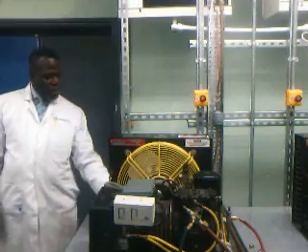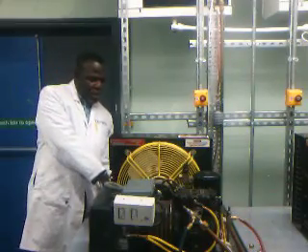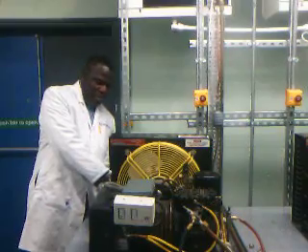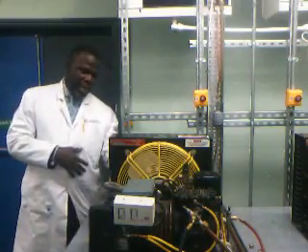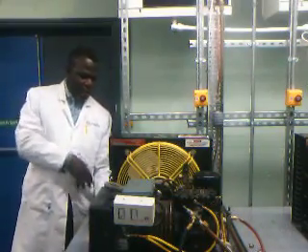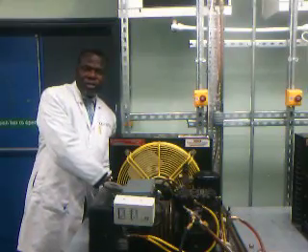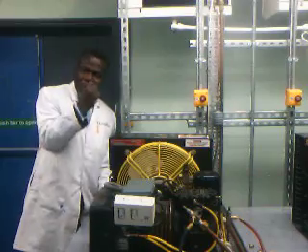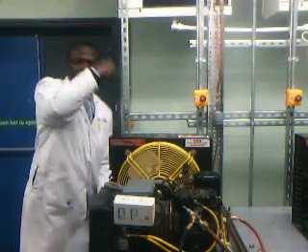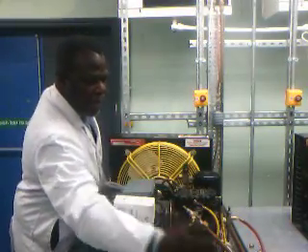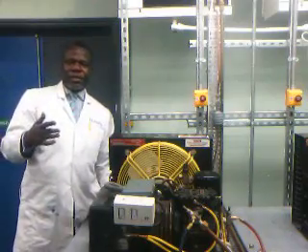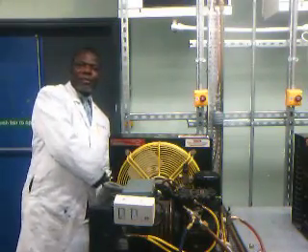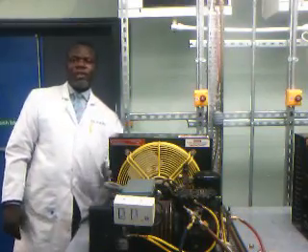Towards the end of the condenser, the refrigerant condenses completely. So you get around here. It's not totally at the end, but it's nearing the end. You have the refrigerant saturated, so you have a saturated liquid, and that is the point where you have the bubble point. So the temperature you record on the high side gauge, which is the condensing temperature, refers to the state of the refrigerant at this point towards the end.